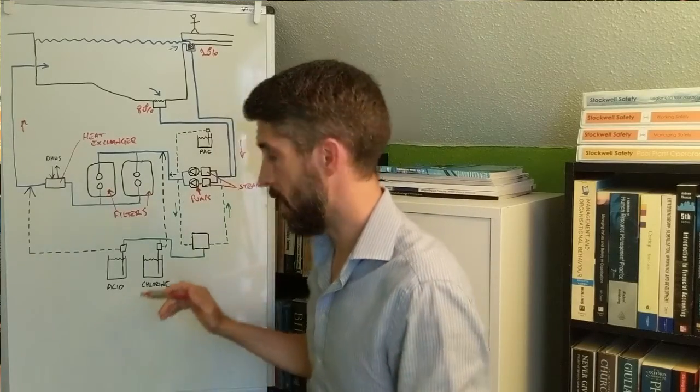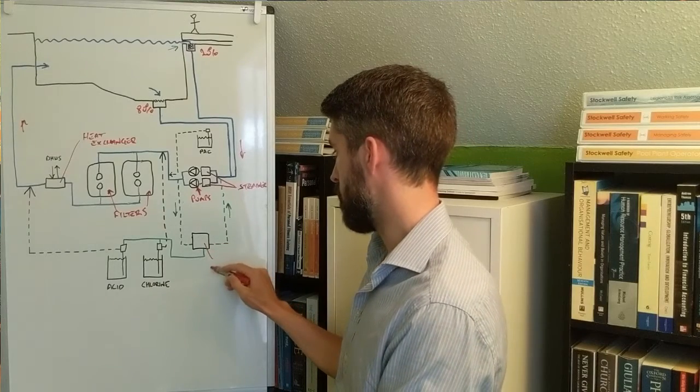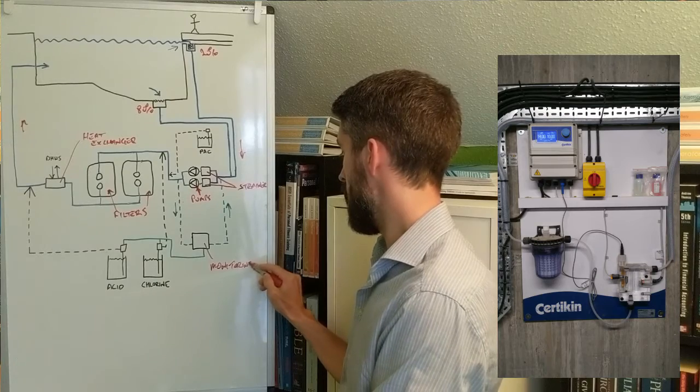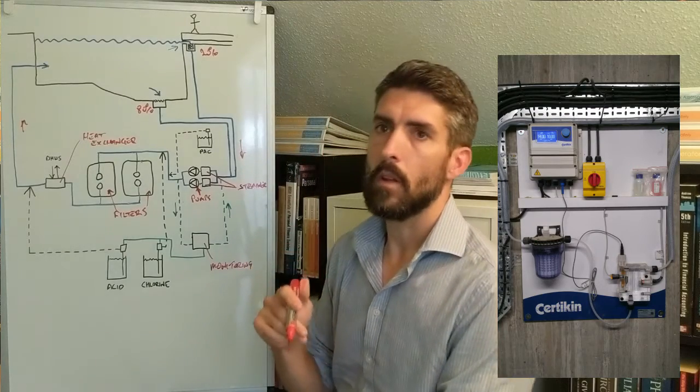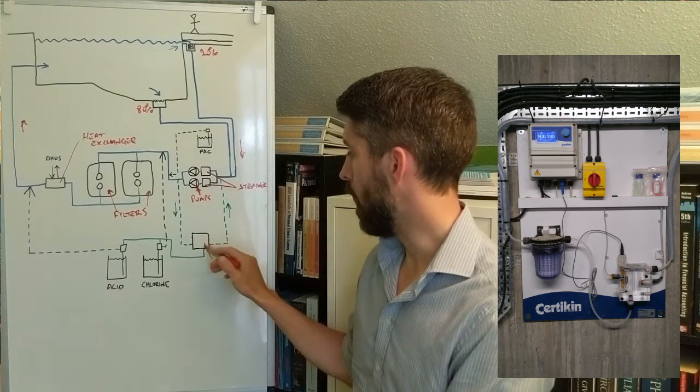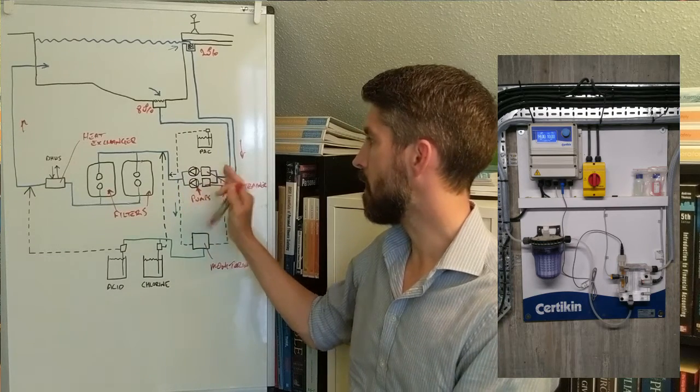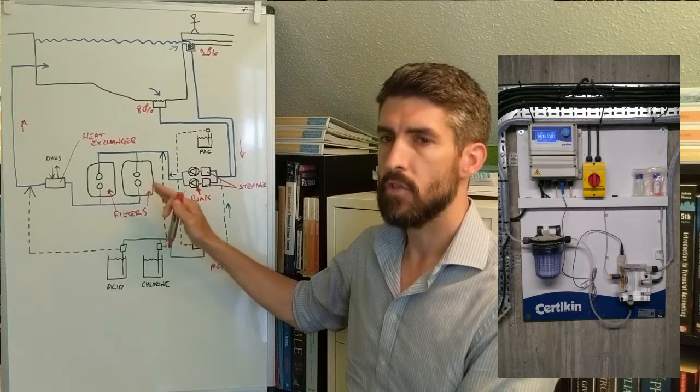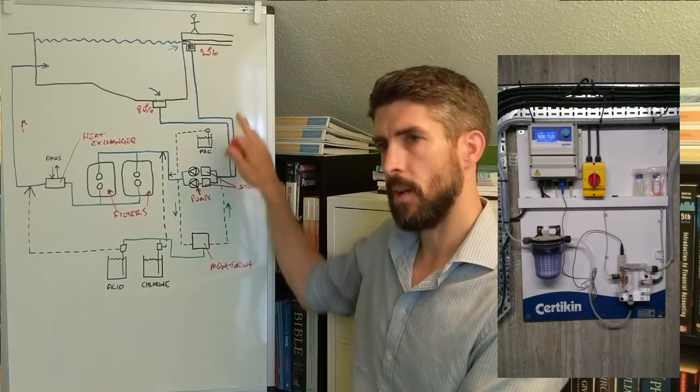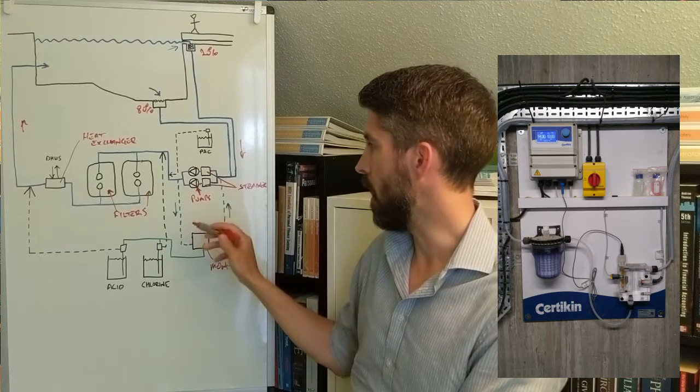Other things to point out: what you'll typically also have in a commercial swimming pool is some sort of monitoring equipment that will be continually testing the pH and the free chlorine level. There'll be a sample taken from the delivery side. Anything downstream of the pump is referred to as the delivery side, whereas anything upstream of the pump in terms of water flow is referred to as the suction side.